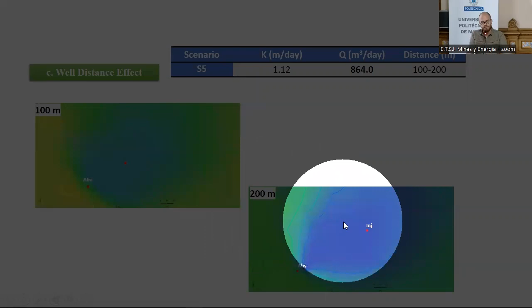The third scenario is the well distance effect. For example, at the left, the distance between abstraction and injection well is 100 meters, and at the second one it's 200 meters. You see the ISO line of thermal interaction reaches the abstraction well - it's very narrow and fluent. But when we focus on the 200 meter case, it's clear and there's no problem. So well distance is another important factor in designing your heat pump system.